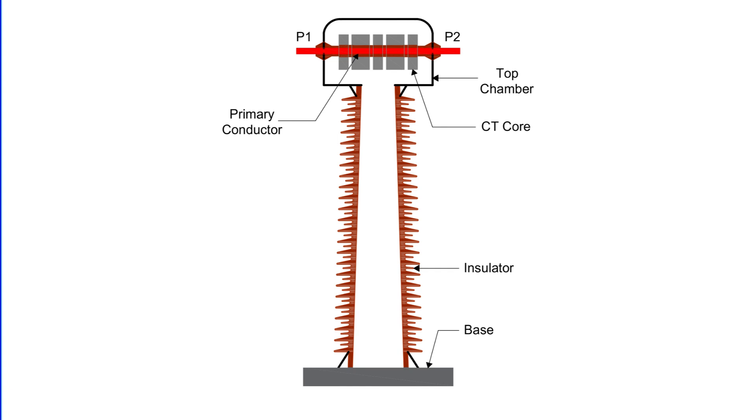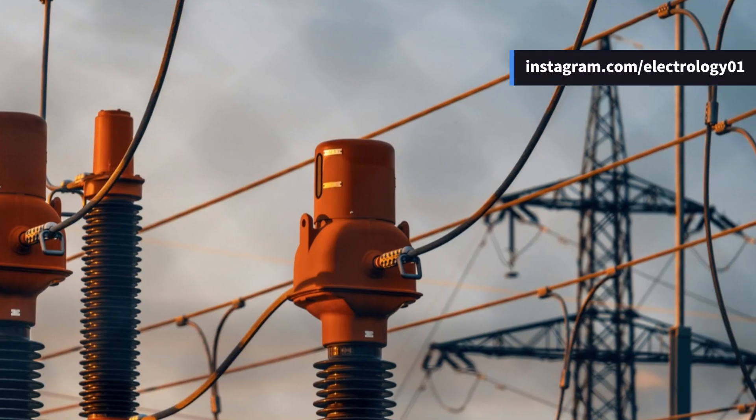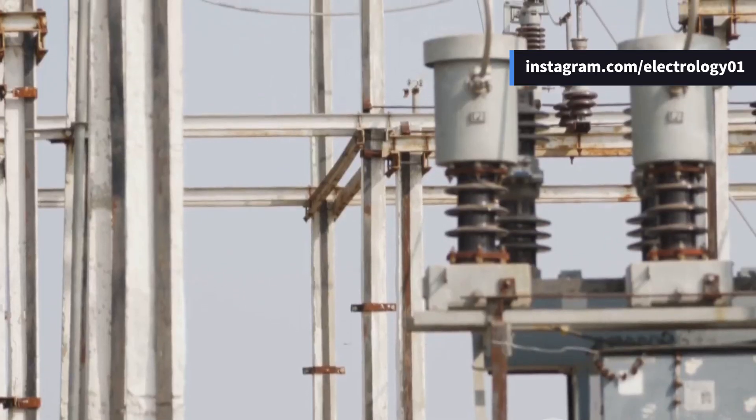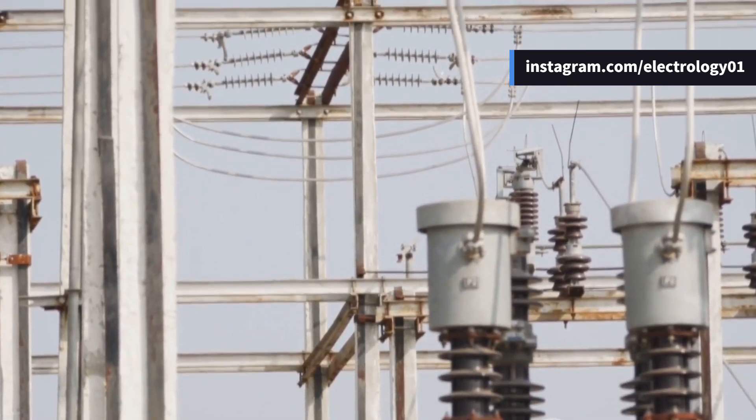But that brings up the question: if live tank CTs are safer and more modern, why do we still find dead tank CTs in so many substations? The answer lies in history. Dead tank CTs were part of older substation designs, and they were the standard in the past due to their ability to house multiple cores and handle higher burdens.